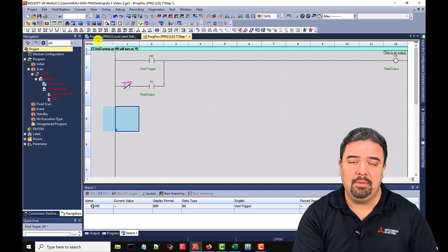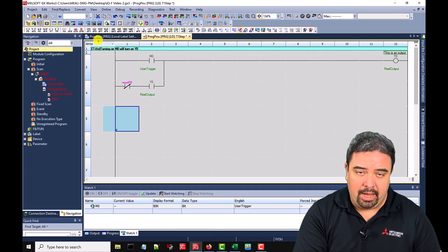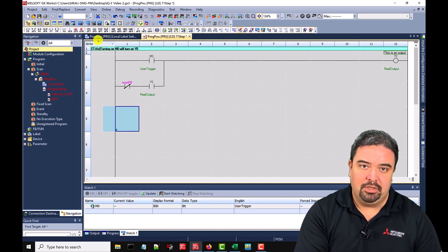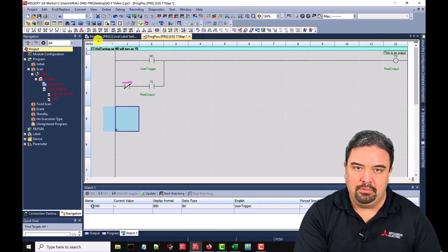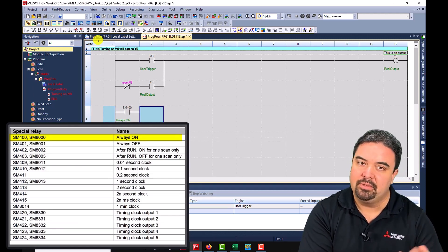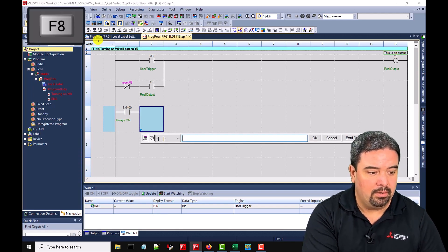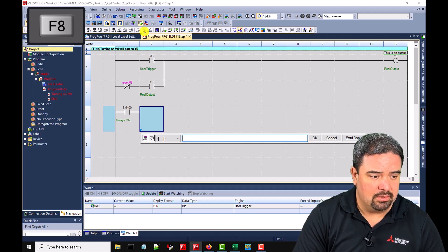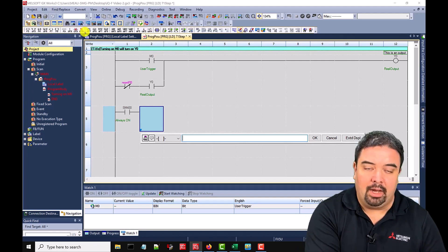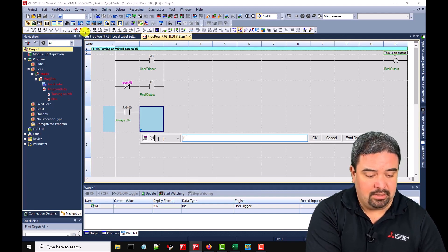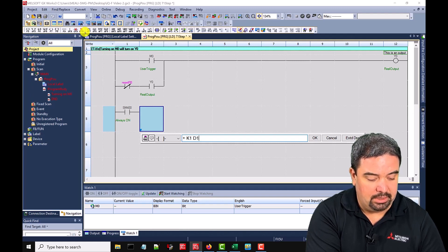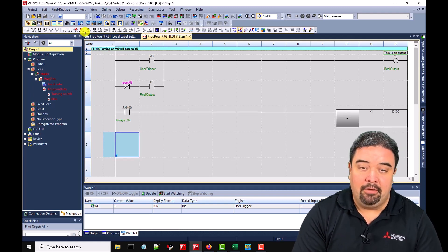Another common thing that you might want to do in GXworks 3 is to use math. I want to show you the way that Mitsubishi originally did it because you might see some legacy projects. So let's go ahead and do an SM400, which is always on. So that bit will stay on no matter what. And we can hit F8 for a coil. I can say add. So I give a plus sign K1 to D100. That's a basic math function.